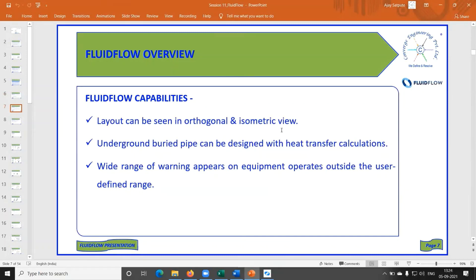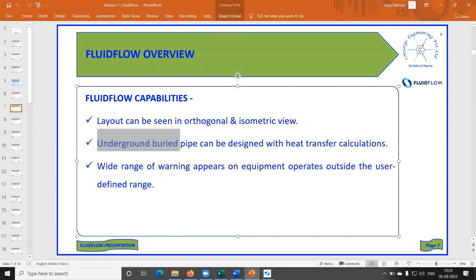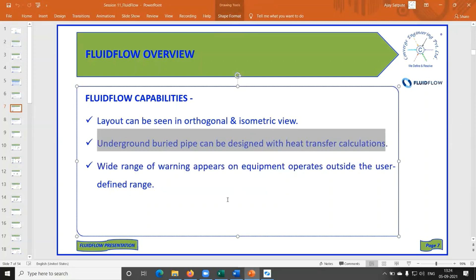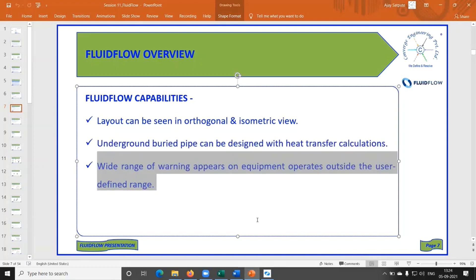Layouts can be viewed in orthogonal or isometric view, and heat calculations can also be performed — for instance, for a 100-meter steam pipe with insulation, you can determine heat loss to ambient and find the economical insulation thickness. Fluidflow also helps identify mistakes in your model: it gives warnings pinpointing which equipment has an issue. If your model is very large and you run into trouble, other software won't help you pinpoint the mistake, but Fluidflow will.